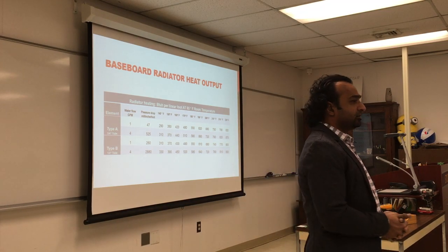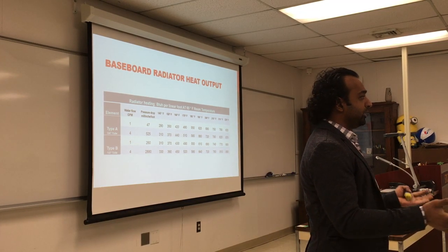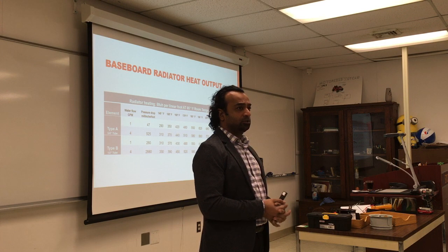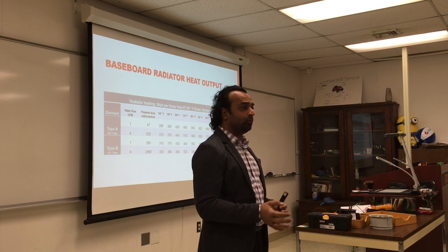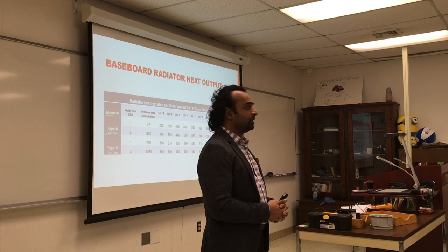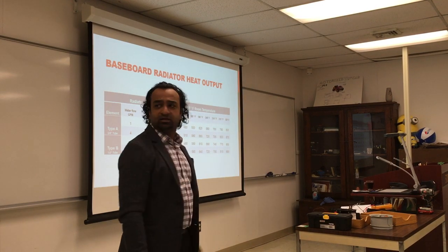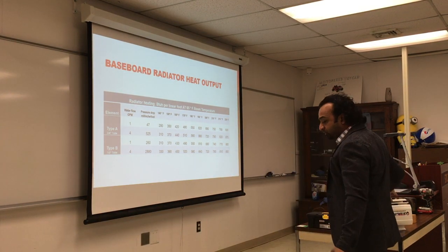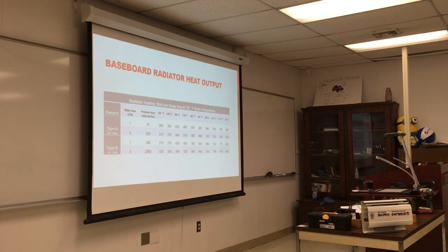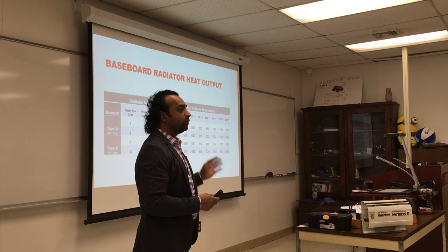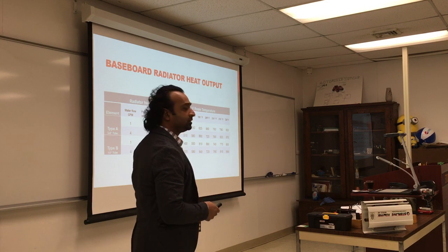Distribution of heat from the boiler all the way to the rooms, and we talked about one of the simplest ways to distribute hot water, which is to send hot water from the boiler all the way to radiators. And we use two types of radiators, the hot water radiators, and they are sized per foot length. Some radiators are sized per square foot or volume, so you have to be aware of how much BTU is being emitted by each foot or each volume, or what unit of distribution we have for the radiators.